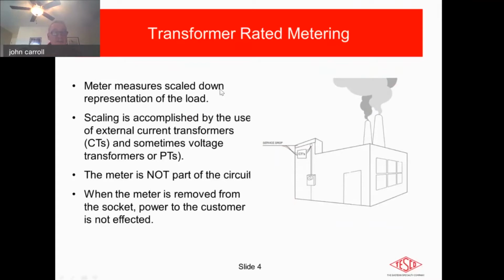Metering really measures a scaled-down representation of the load. A little pictorial representation of a factory is given here as an indication of the meter itself, the CTs and the service drop. So really what we're doing is scaling it down, in order to make it safe to work on. All of this is done through CTs and also VTs, which are voltage transformers. And all of this is done, obviously, with accuracy in mind.